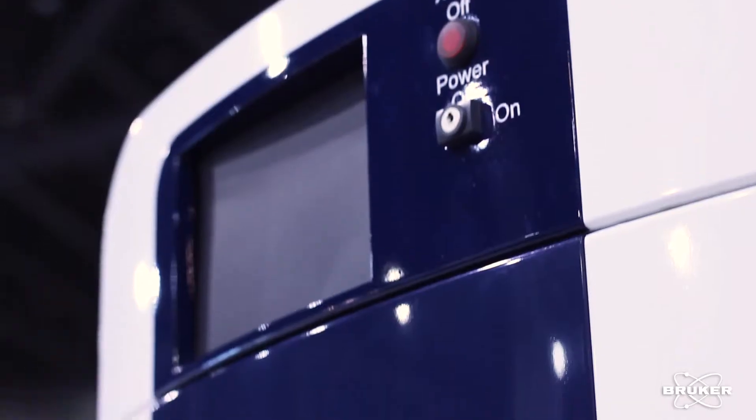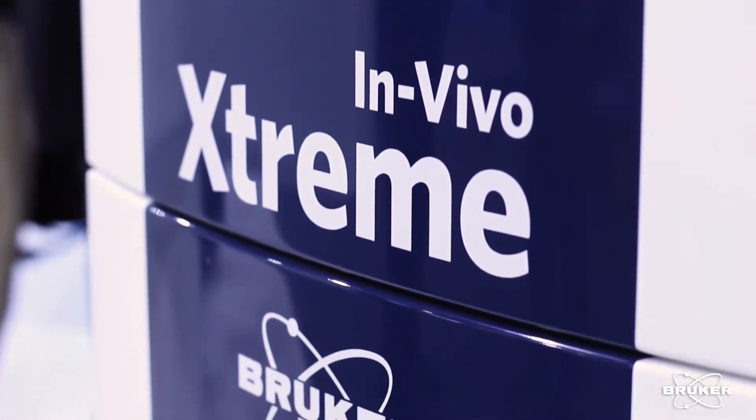The system itself, the Xtreme, is also equipped with 28 excitation filters that cover the whole range from the visible to the near infrared light. With that, you are able to address roughly every fluorophore that is available in the market and that you produce yourself.